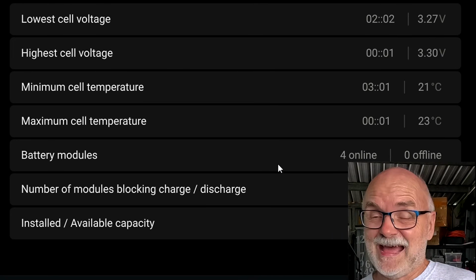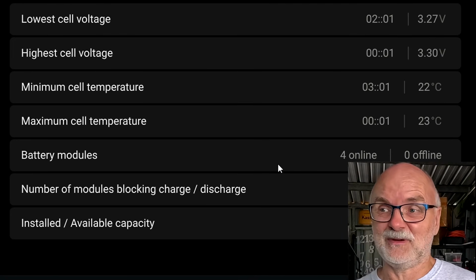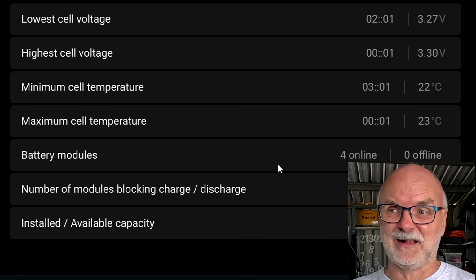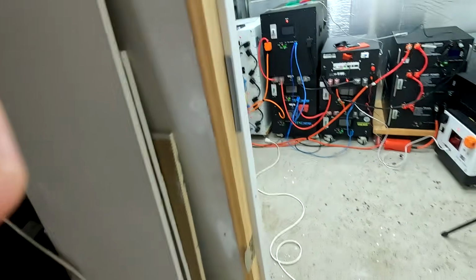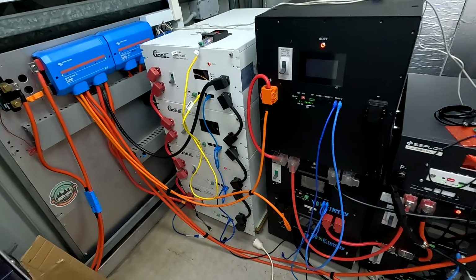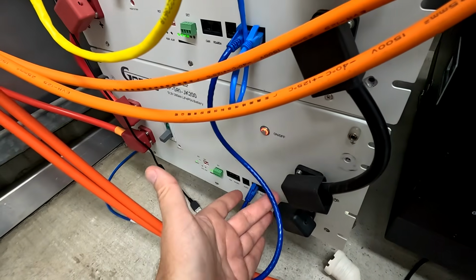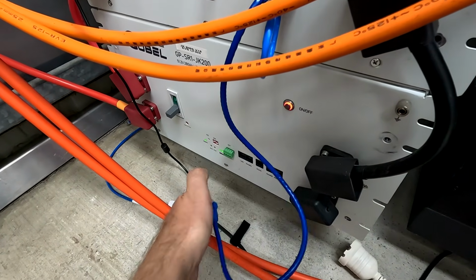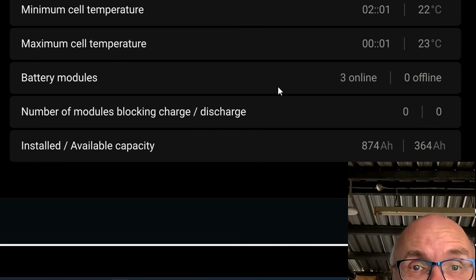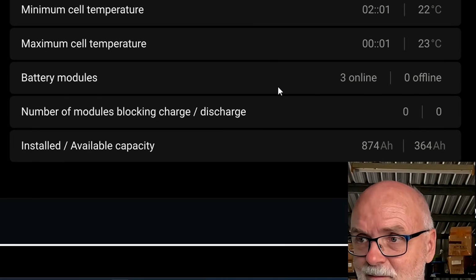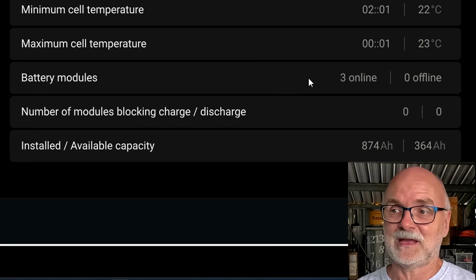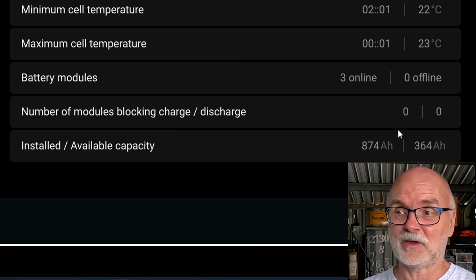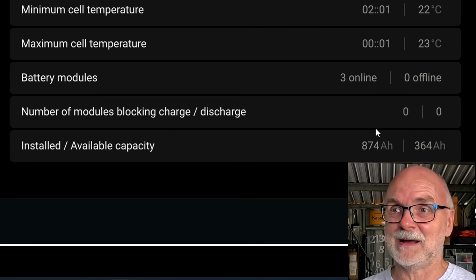So now there could be another fault. So far we have tested internal faults with the cells: over voltage, over current, over temperature stuff. There could be something else happening to your system. You've got this stack of 4 batteries and now you have a fault in the cable. Someone unplugs one of the cables accidentally. One BMS goes missing. What you can see here already in the Victron remote console is that the master BMS now says there are 3 batteries online. Nothing is blocking, there's not even an alarm coming up.